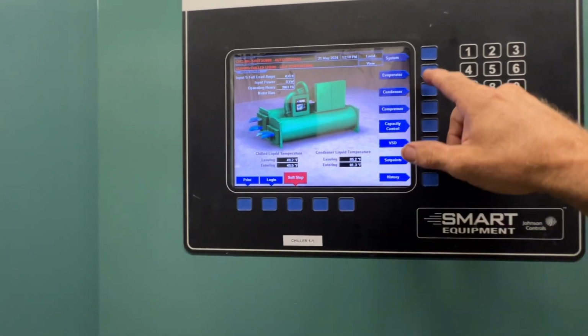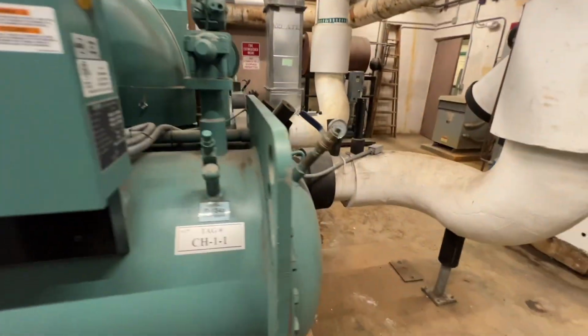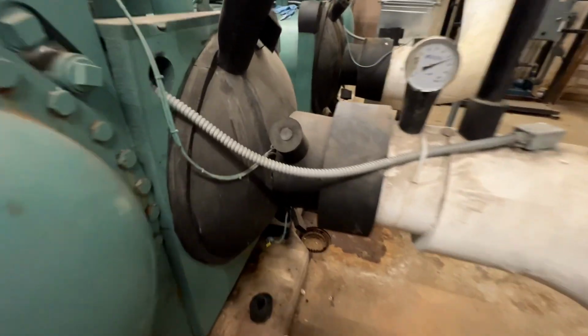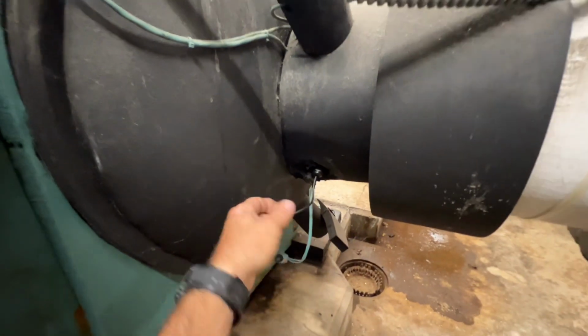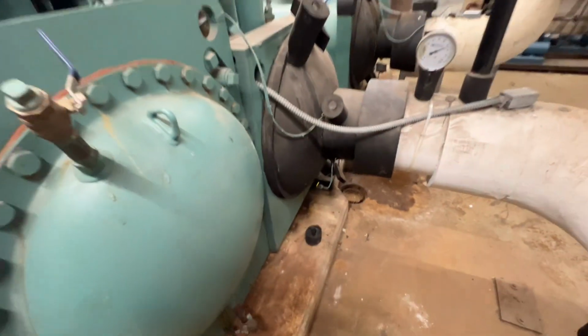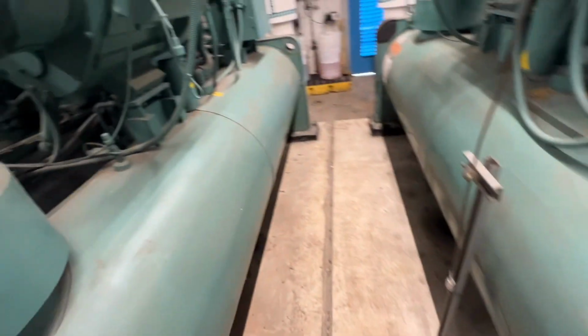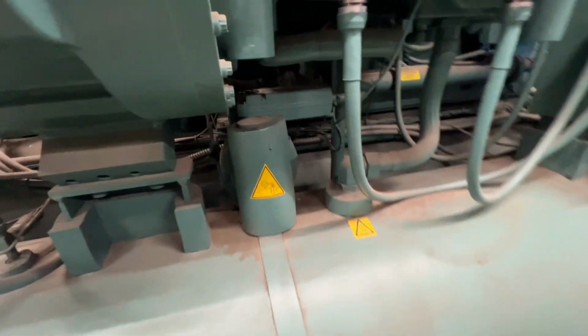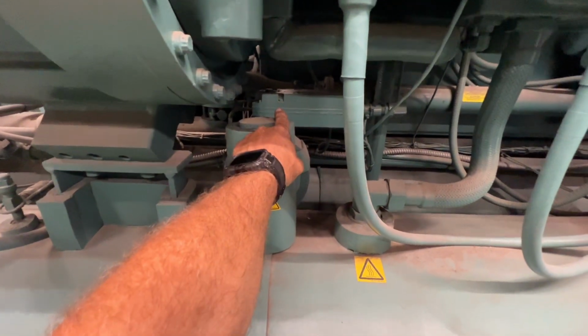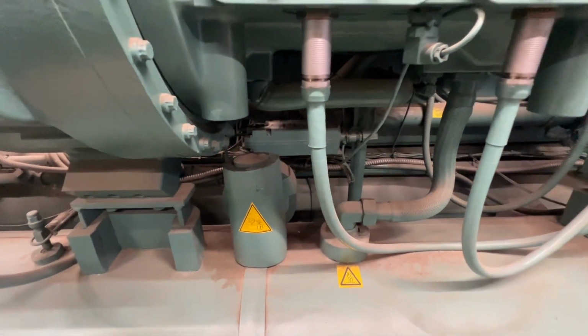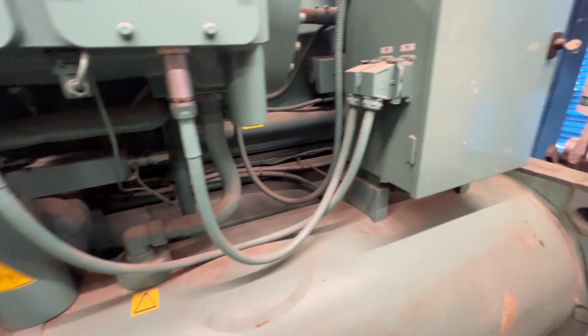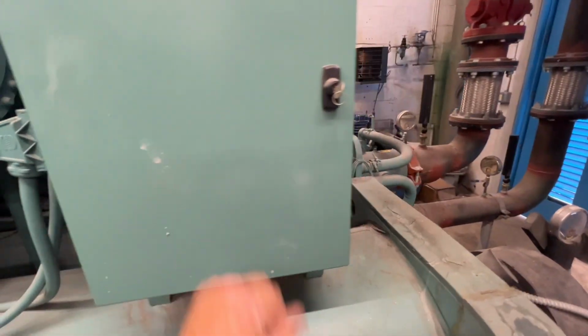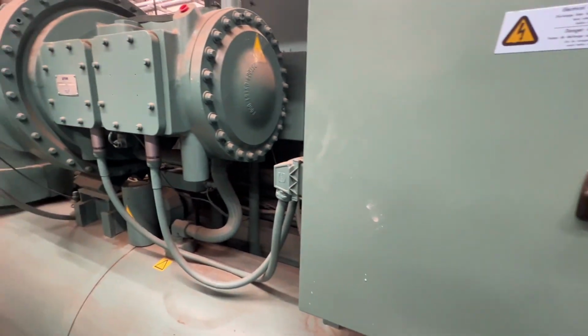He did also change our entering water temp sensor on chiller 1, and he did verify that our control valve was operating, opening and closing properly. And like I said, he did his recalibration here for that rotor.